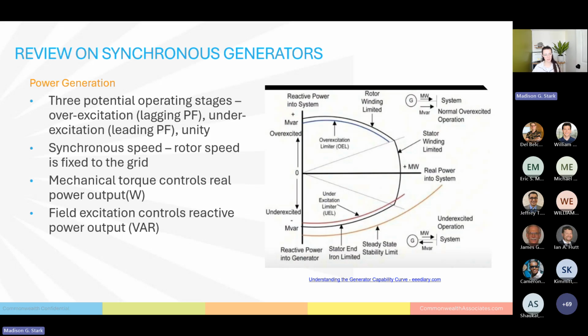So these two inputs that we have, the mechanical torque and then the field excitation, control different components of the output of the generator. Your mechanical torque is really what controls the wattage, the real power output of the generator. The field excitation, that DC excitation on the field windings, is what controls your reactive power output. So this is how you're going to manipulate the excitation of your generator via those field windings and that DC excitation, which is important.